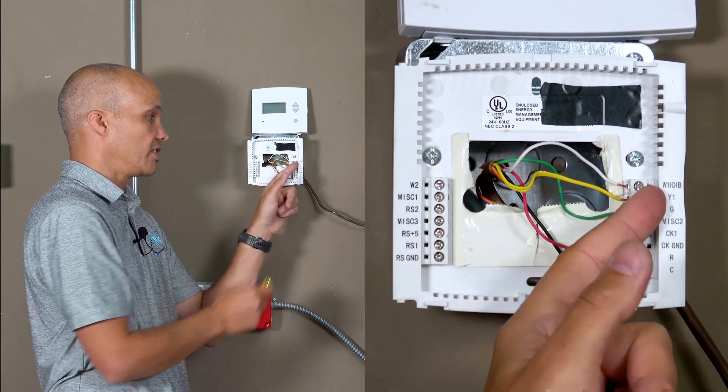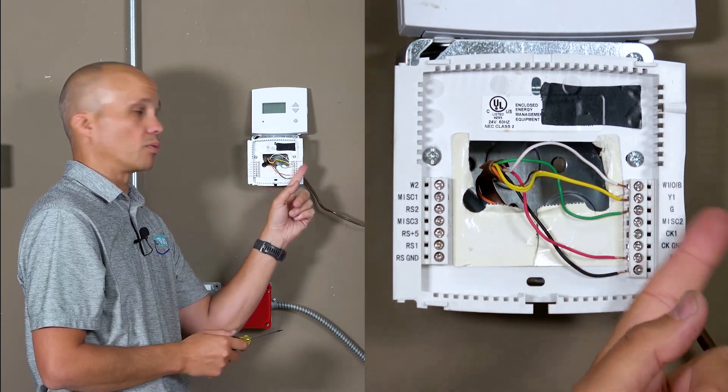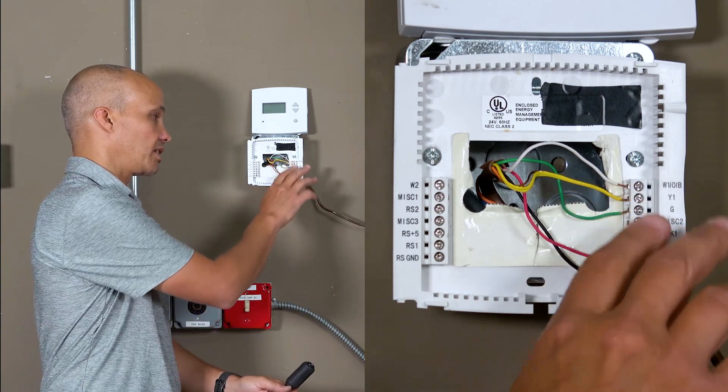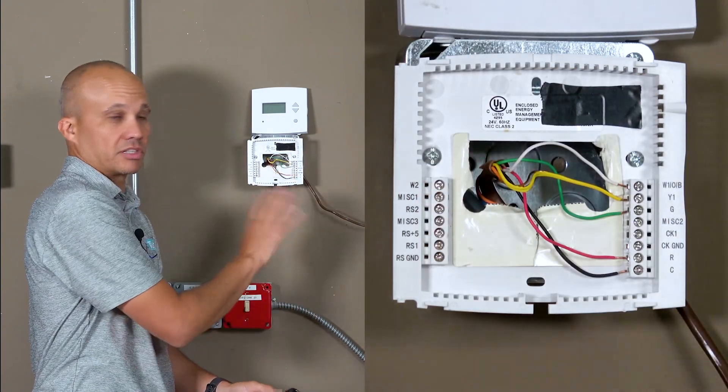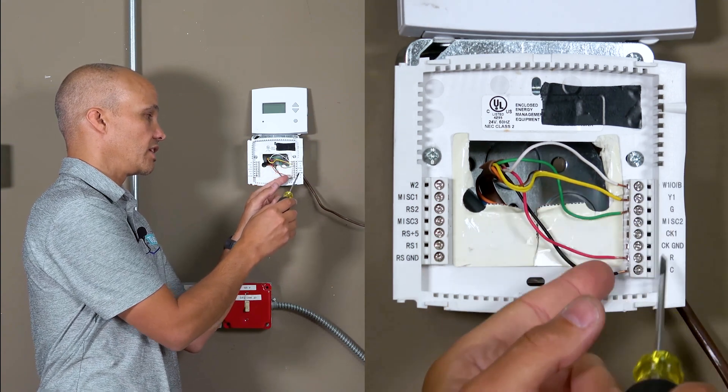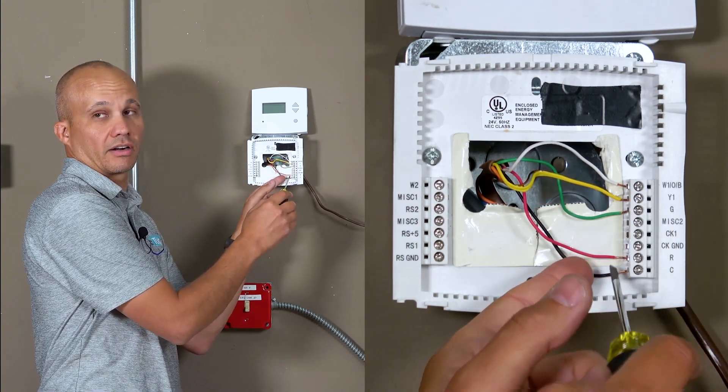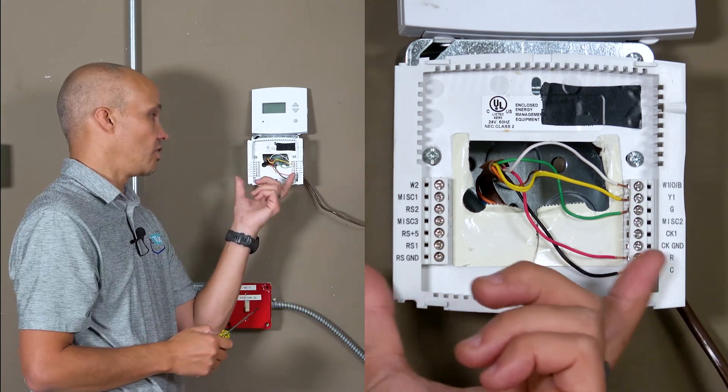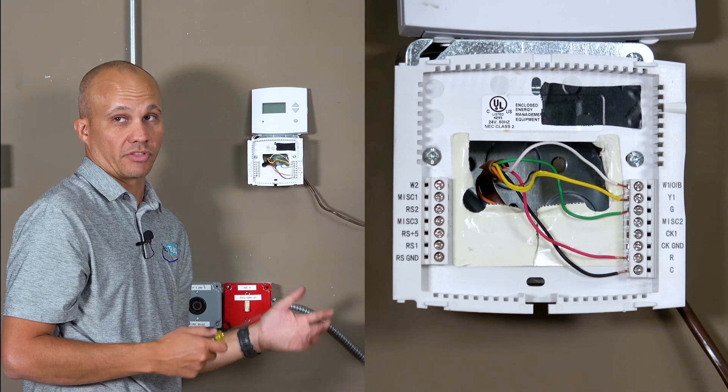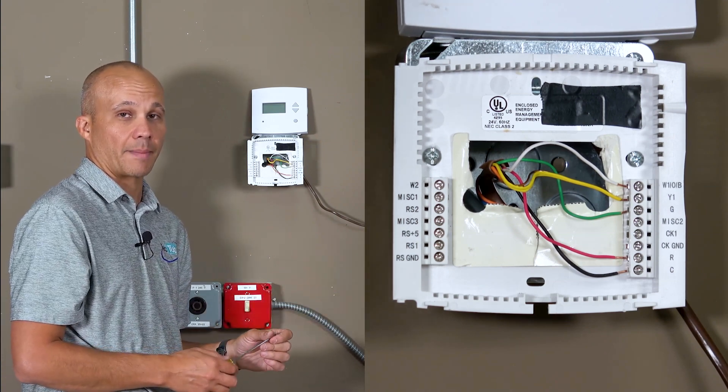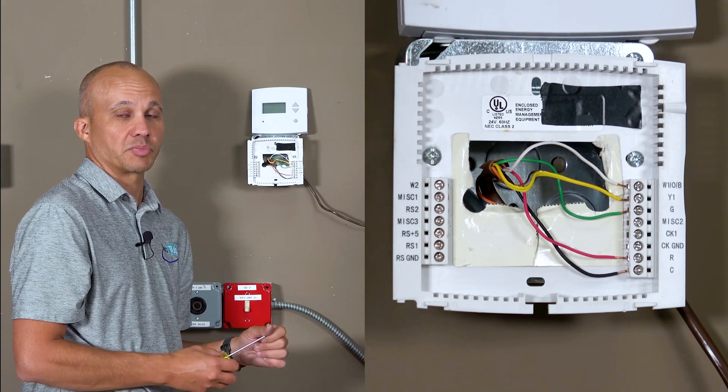Down here on this stat it happens to be labeled W1 slash OB. In our application we only need the W, so we're going to pick W. OB is a different application, you program the stat differently. Yellow is going to Y1, green to G, red to R, and then we have black going to common. We've got to match those five up. You'll notice this stat has plenty of other wires on here that we're not using, other terminal spots. Those are for different applications. That's fairly common that you're not using everything of the specific models that you've chosen.